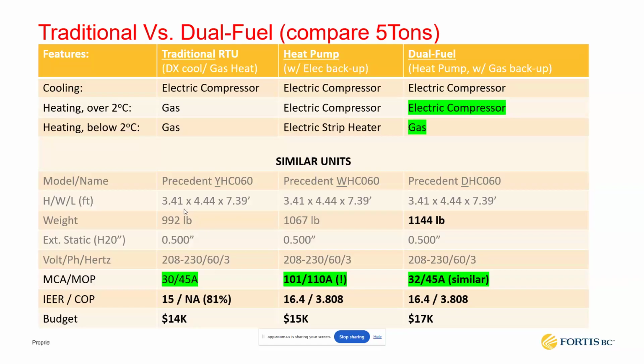This is a comparison of a dual fuel. The column on your left here is the traditional rooftop unit with DX cooling and gas heat. In the center, you have a heat pump with electric backup, a fully electrical unit. And then at your right, you have your dual fuel with gas backup. Couple of things to look into: number one, this unit is going to be a bit higher on weight, although not too much, around 15%. And the unit will be more expensive, because this has the addition of the heat pump.